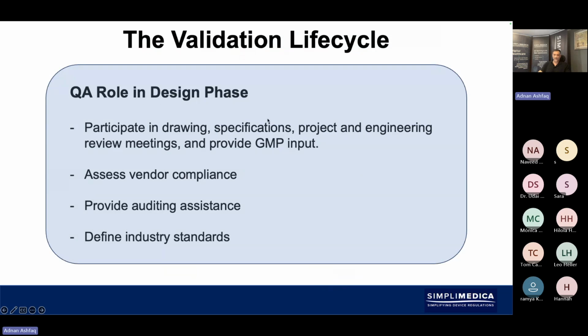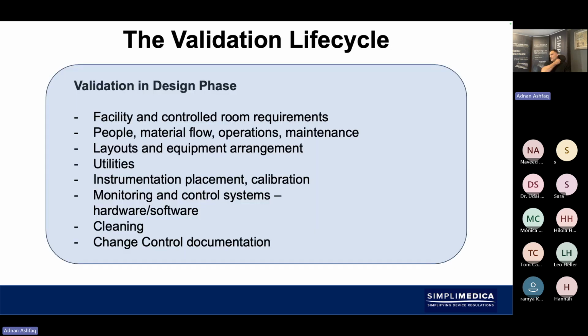So there are also roles and functions involved in the different phases. There's a role for QA in the design phase to make sure there's participation in drawings and engineering meetings. There's an input from good manufacturing practice. There's also an assessment of vendor compliance. The vendor or supplier that you choose for your supply of the equipment also needs to be approved, and they may need to be audited. They also need to have industry standards defined. So there's a very important contribution there from quality assurance.